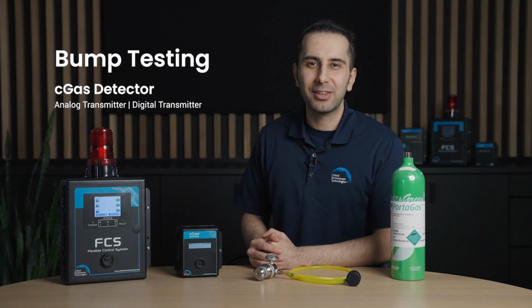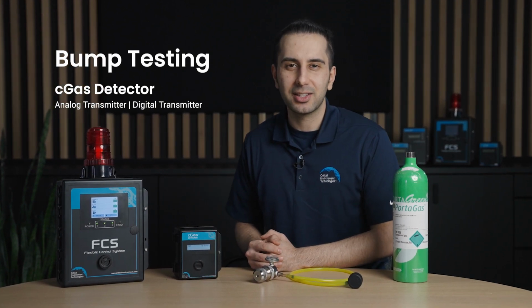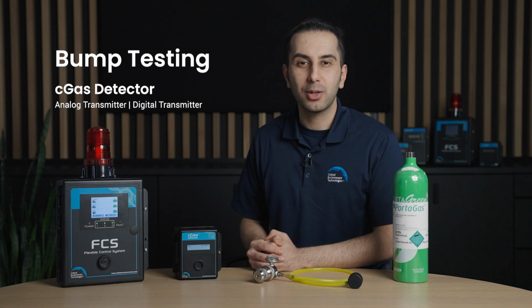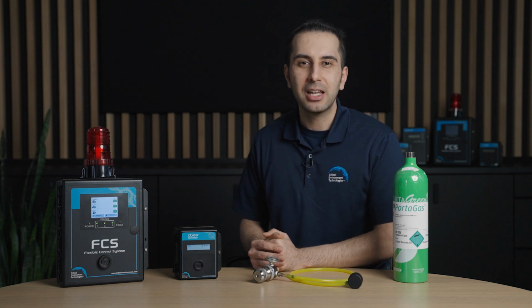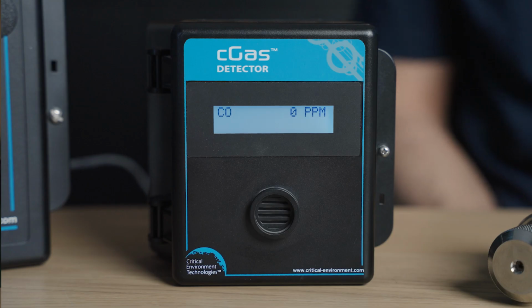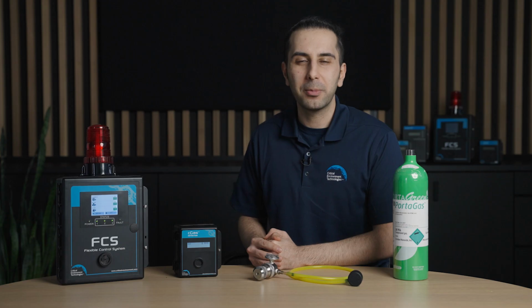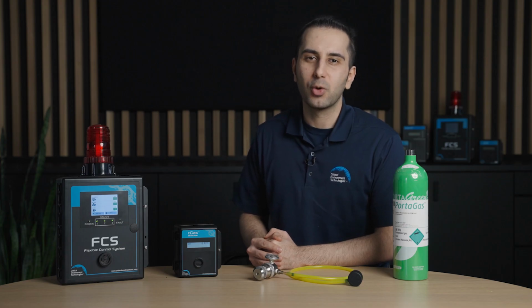In this lesson, we will navigate bump testing on the C-gas detector. A bump test is a quick check with a known concentration of gas to make sure your gas detector is working properly. To perform a bump test, you will need these pieces of equipment.